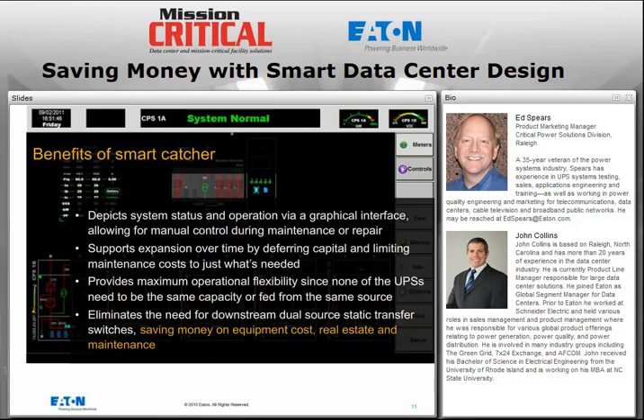the largest single UPS. So this provides the maximum operational flexibility since the UPSs don't need to be the same capacity, and by the way, they don't have to receive their input from a common source. I may have several input sources in a facility, and the UPSs, as I've deployed them over time, may be getting their input from different places. The catcher system doesn't mind. It can operate successfully regardless of where those sources are. So these kinds of things allow the more typical type of growth pattern that we see, where the growth is not planned to the nth degree 10 years out. It's a hodgepodge of additions and moves and changes and different requirements and changing loads and virtualization and all those kinds of things. We need a system that can flex very easily and without forcing the client to over-provision at any point along the way.